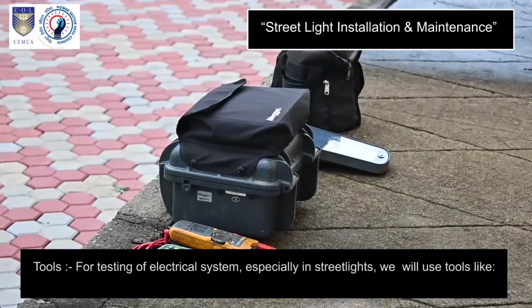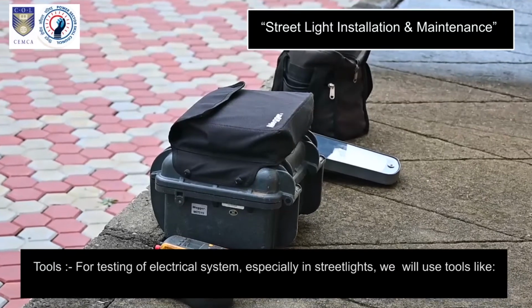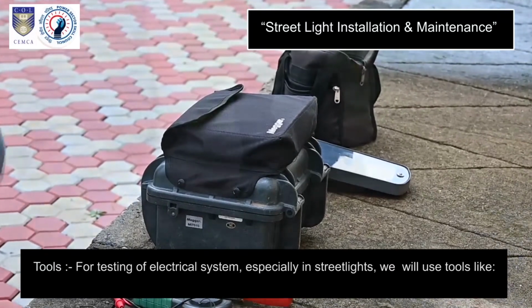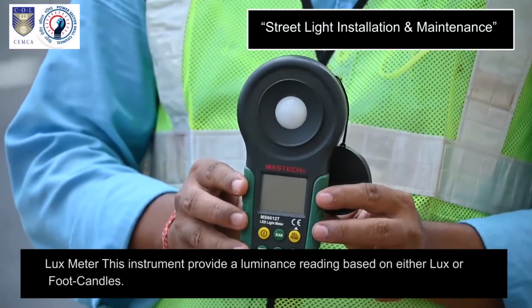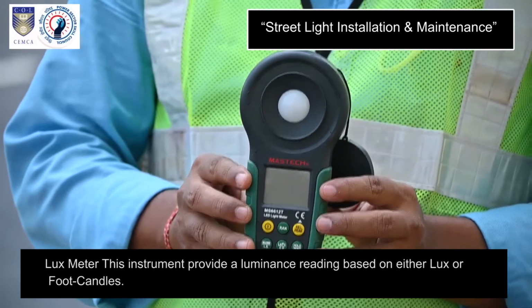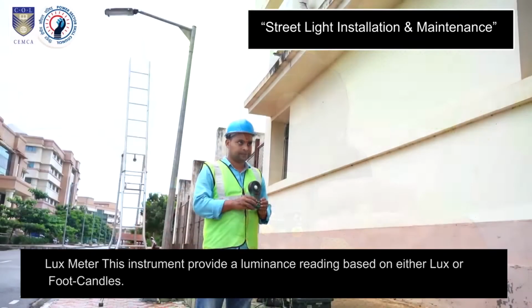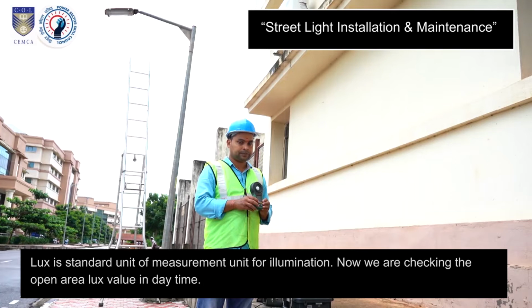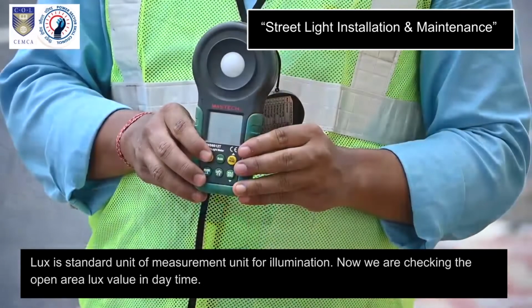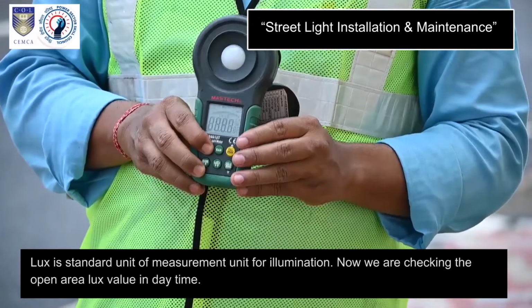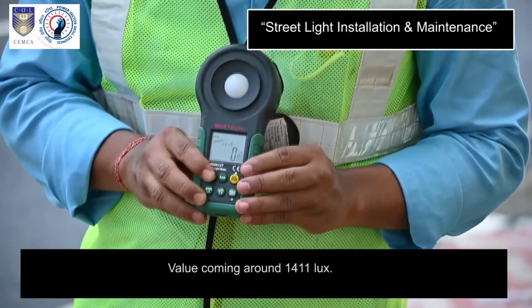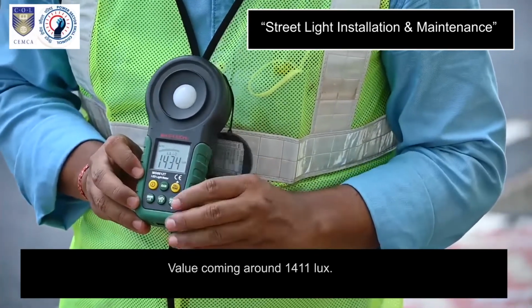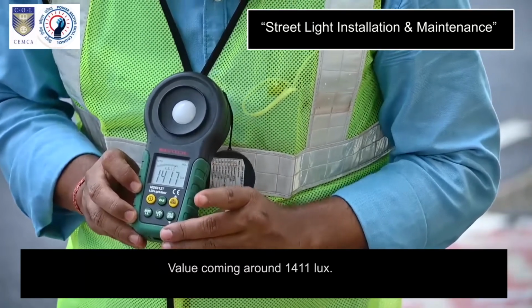Tools. For testing of electrical systems, especially in street lights, we will use tools like Lux Meter. This instrument provides a luminance reading based on either lux or foot candles. Lux is standard unit of measurement unit for illumination. Now we are checking the open area lux value in daytime. Value coming around 1411 lux.